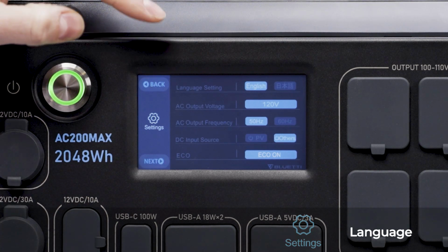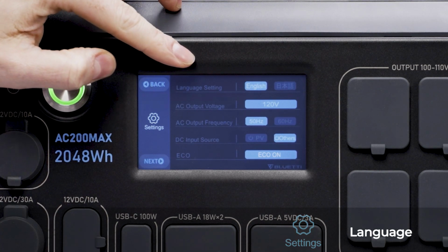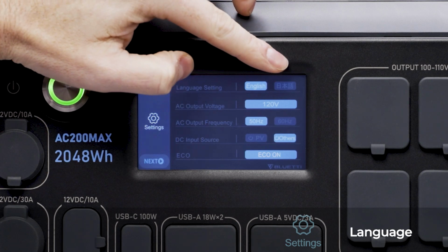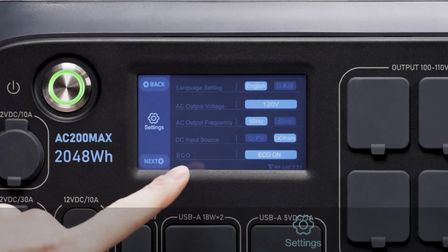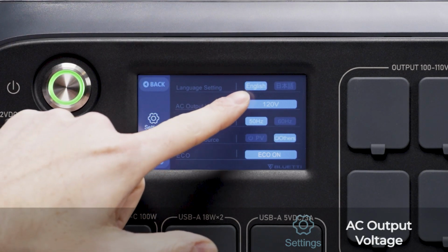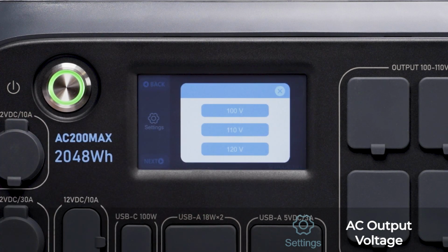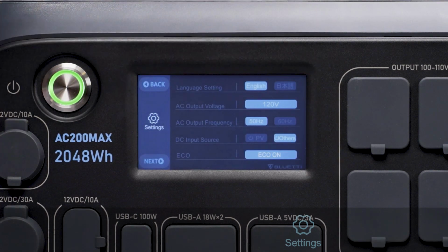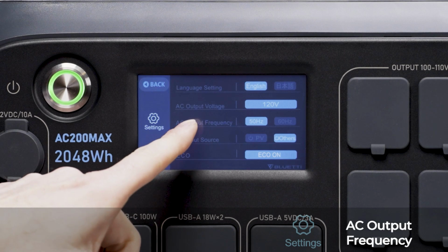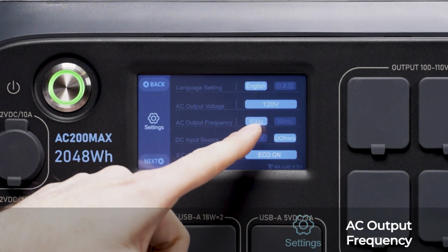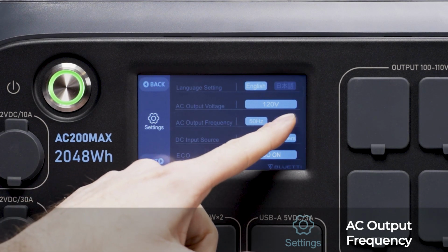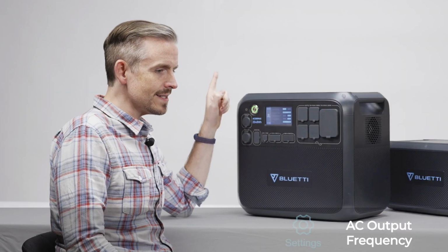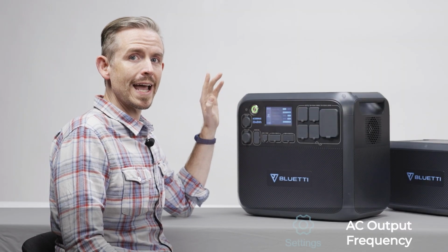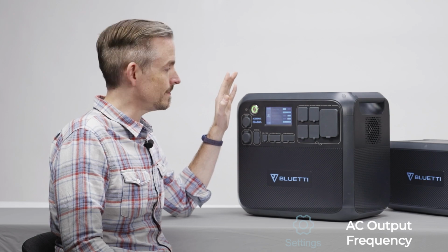The first setting is pretty clear. It's language, which can be switched between English or Japanese. The next one is the AC output voltage, which you can click to select between 100 volt, 110, or 120 volt. AC output frequency can be switched between 50 hertz or 60 hertz, but this setting can only be changed when the AC output is turned off.